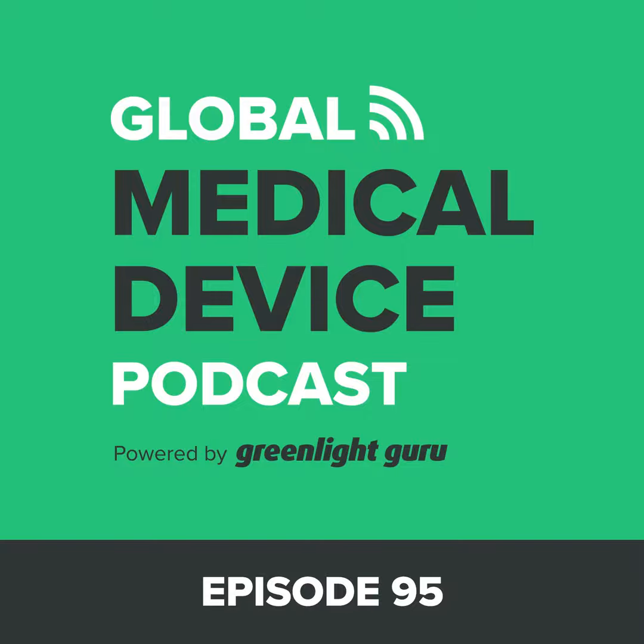You can see things that happen also in the field where if there's multiple devices used in a system, each device is independently validated and independently approved. And when it becomes a complex system, if you go into the OR or the cath lab, you'll quickly realize that there are technical sales reps running around providing technical support. Why are they there?